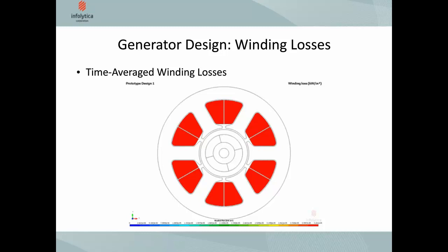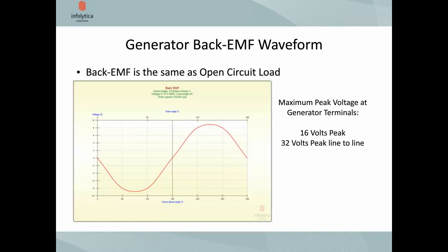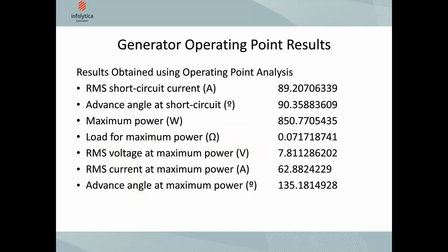The most important quantity to start with from a generator is its back EMF. Looking at the back EMF waveform, we want it as close to sinusoidal as possible and to reduce ripple. Here is the back EMF waveform for the high-speed generator — it has a 16-volt peak phase voltage, or 32 volts peak line-to-line. The operating point results for this generator show the short circuit current and maximum power of about 850 watts, plus other quantities such as the actual power at the generator leads before the diode bridge.